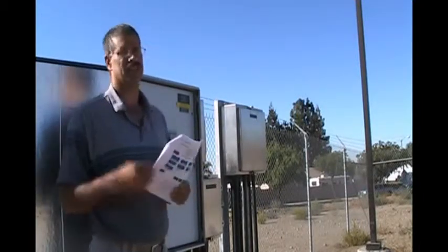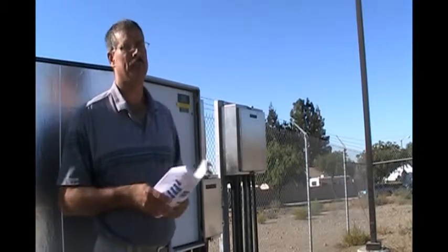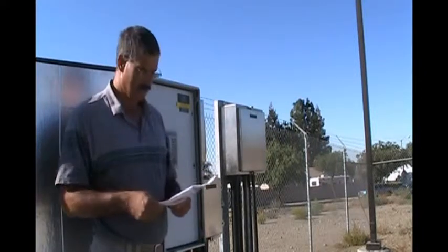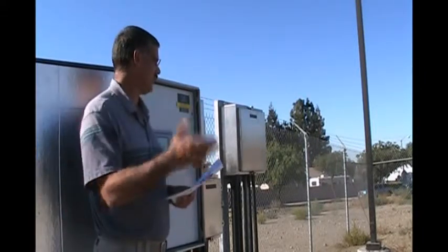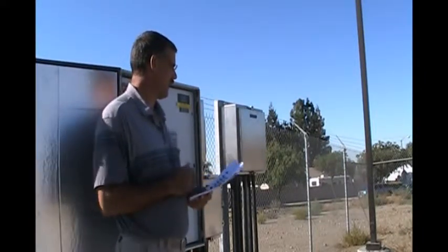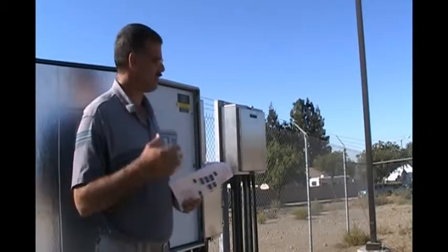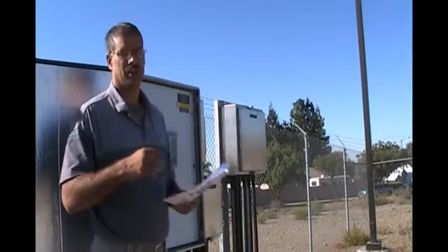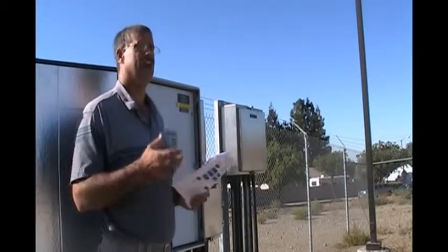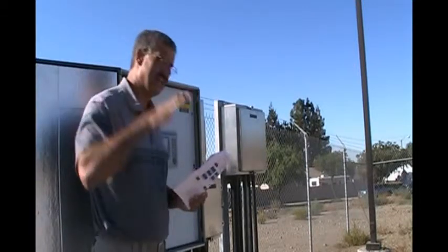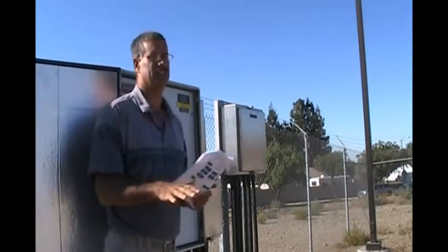Doesn't mean you have to set your alarm set point there. You can set it to whatever you want, but I somewhat recommend that be around 60 or above, so that you get an indication that the valve is shutting off when that alarm comes in. Now, over at Orchard Street, we found that they decided to set there's a mechanical shutoff on that valve as well, such that if the valve itself detects a certain pressure, that it will shut off. This should be a secondary safety.